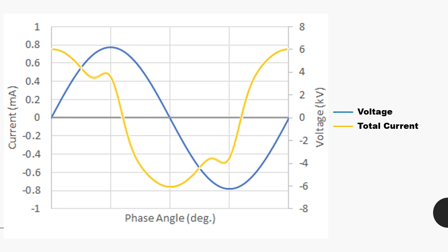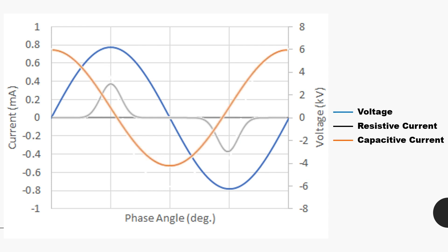Leakage current of arrester has two components: resistive component which is in phase with the supply voltage, and capacitive component which is in lead with respect to the supply voltage.